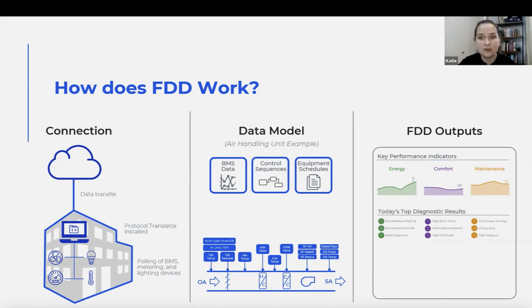And then it'll say, okay, of those, these are the top things, right? So if energy is very important to your campus, these are the top things that you should be responding to: the simultaneous heating and cooling fault, this economizer override fault, and this reset sequence. And you as an organization can decide where your priorities lie and what you should be responding to, so that you don't get weighed down by alarm fatigue. You want to be able to prioritize and make smart decisions about where you spend your time and how you do your work. And then finally, it'll give you a cost savings. Typically, that's energy savings at this point in the industry. I think there's a lot of conversation around where that can go outside of just energy, but at this point that is typically where they're talking about cost savings. That's another thing to ask your provider as you're interviewing folks.